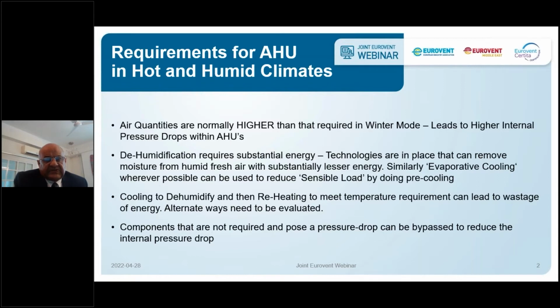Dehumidification requires substantial energy. Technologies are today in place so that moisture from fresh air can be taken out with substantially less energy. Similarly, evaporative cooling, wherever possible, can be used to reduce sensible load by doing pre-cooling. Cooling to dehumidify and reheating to meet temperature requirements can produce a lot of wasted energy. Therefore, alternate ways need to be evaluated. Components that are not required and pose a pressure drop can be bypassed to reduce the internal pressure drop.